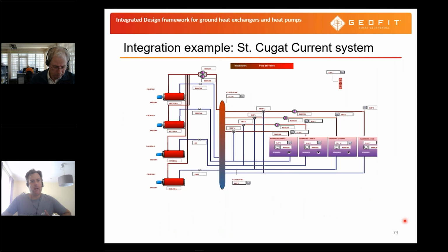So I'm showing now an integration example. It's a little teaser to next week's training, where you will find out more details about the pilots. So here, as an integration example, it's called the Sant Cugat current system. Sant Cugat is the school, and the current system in the school that is near Barcelona. It consists of four gas boilers, some of them as backup, so not four are always running. So we have gas boilers, we have a certain header pipe here, and we have different heating zones. In total, 4 heating zones with those different building categories which are supplied by those heating zones.